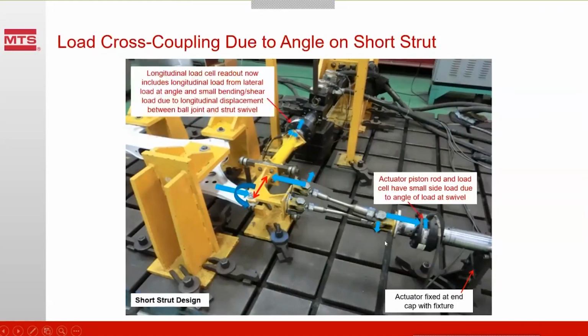That shear force, of course, provides a load to the load cell and the actuator, but it's a relatively small load compared to the force we had to bend that link the same distance. And of course, we've got a little bit of an error here, too. Our compression load now gives a little thrust load. That thrust load is read by this load transducer. So if we knew the displacement and this force, we could compensate for that load, but that's rarely done.